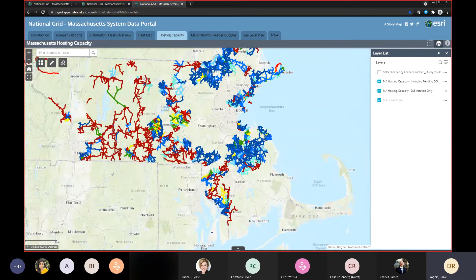Now, the future update, which I'll go into in a minute, would basically take this line right here and see it's all shaded for 5.2, which is really just the max hosting capacity that is located at the substation right here. Instead of having that one broad number that is an upper limit, we would now have segmented analysis. So most likely, if there was a recloser here that did not have voltage supervisory control, this downstream section would be color coded much lower for hosting capacity unless that had got updated.